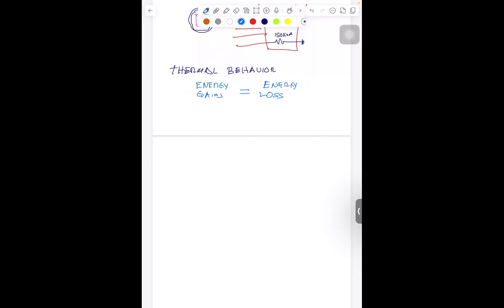Energy gains in a transformer, let's say, will be resistance times current squared, that's the resistance of the winding and the currents in the windings, plus losses in the core. Are there any other losses in a transformer? There could be, depending on the size of the transformer, dielectric losses.